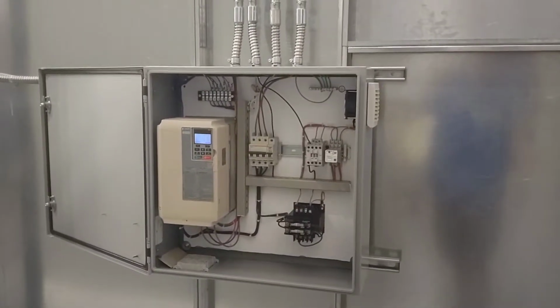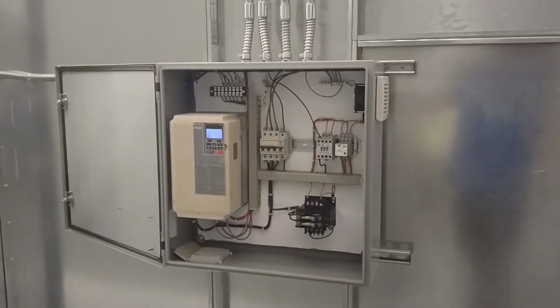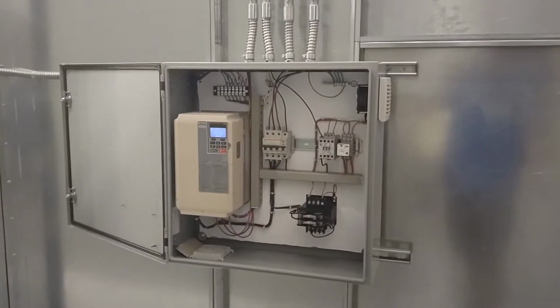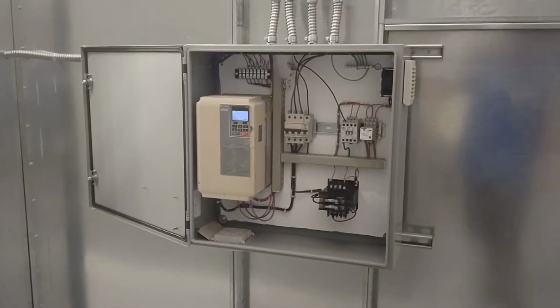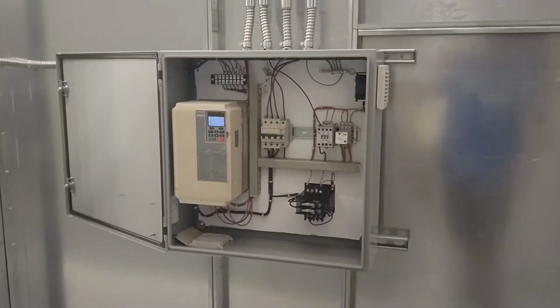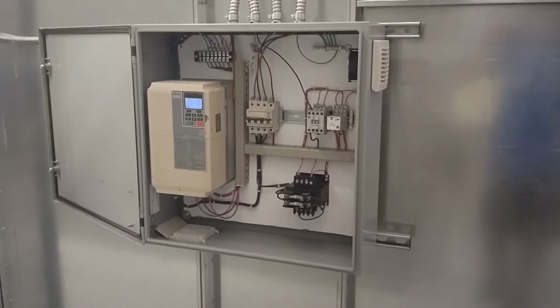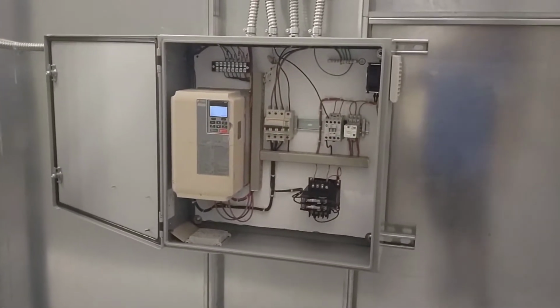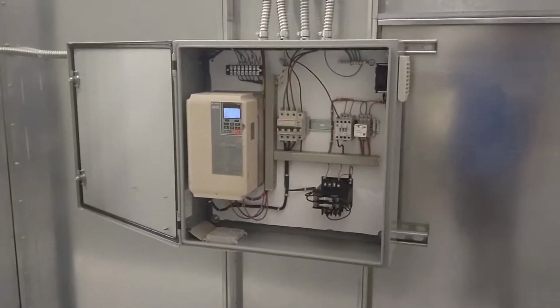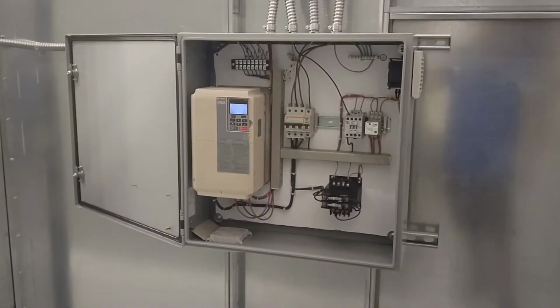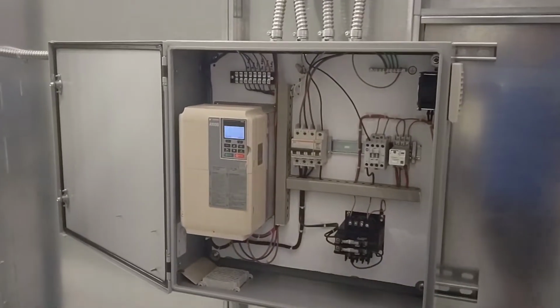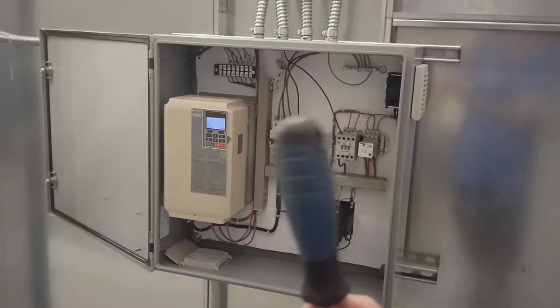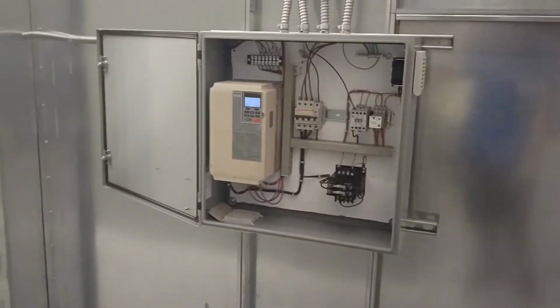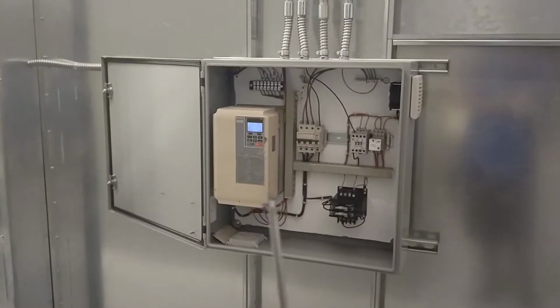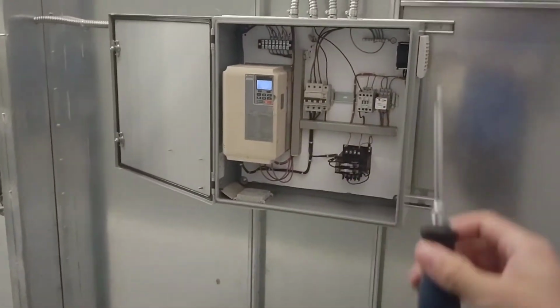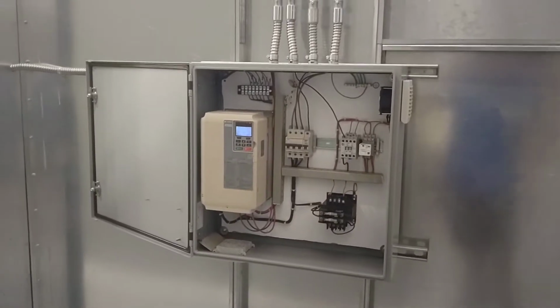So in setting up this system, there's a couple things I had to hit in the programming on this VFD to make sure that everything was going to run smoothly. One of the first points would definitely be that I don't want the fan motor to spin too slow. The motor is VFD rated. However, when you spin a motor slower than it should be spun, you risk overheating the motor because there's a little impeller inside that motor that blows air over the windings. And if it spins too slow, then you're not going to be moving any air over that motor, and it's going to get quite warm.